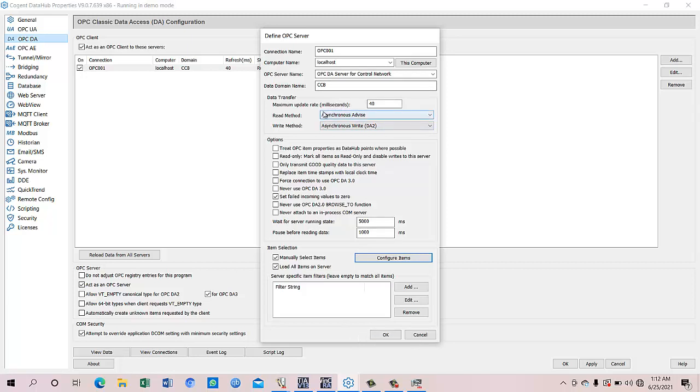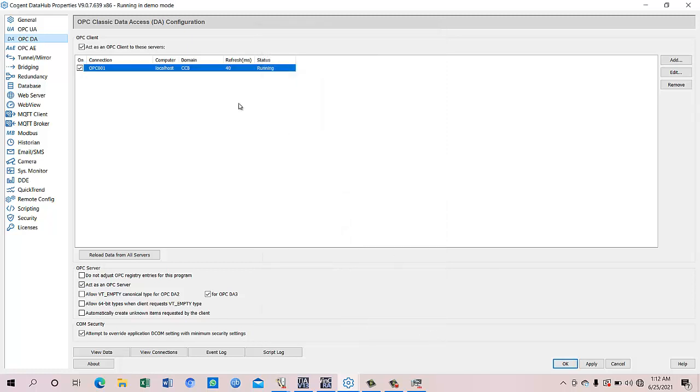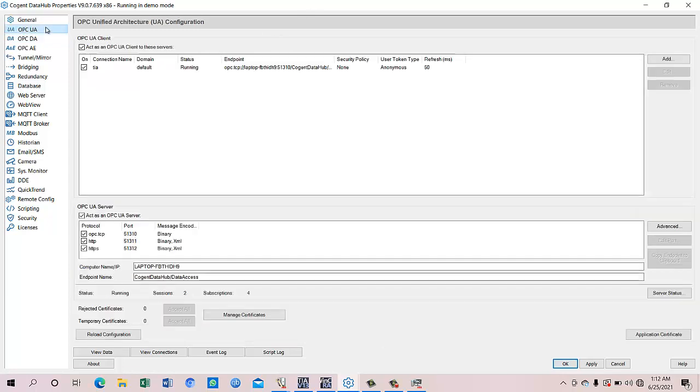So we given the update at 40 millisecond because OPC DA has to be faster than the OPC UA. So we can see now this is the OPC DA configuration is running and we apply this. We apply and it will show it is running. That means my Cogent Data Hub is already receiving data from the OPC DA, that means OPC for the AC 800M. So now I have to make this OPC UA update. So I started an OPC UA.